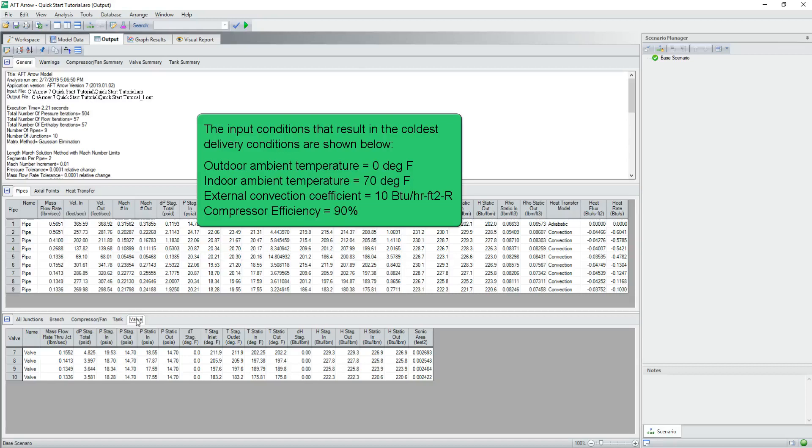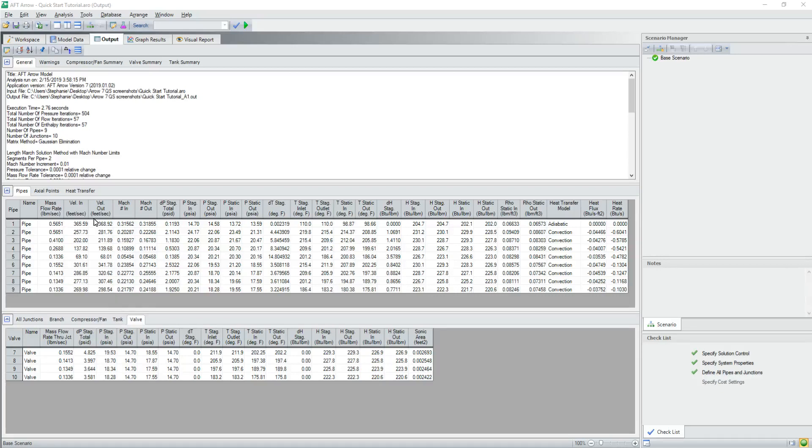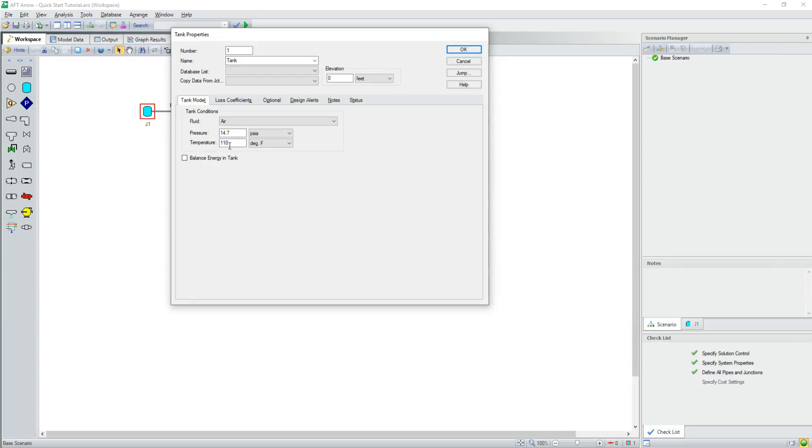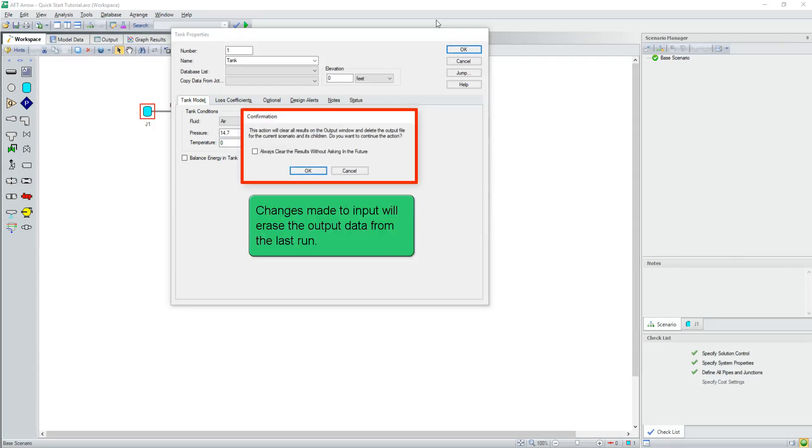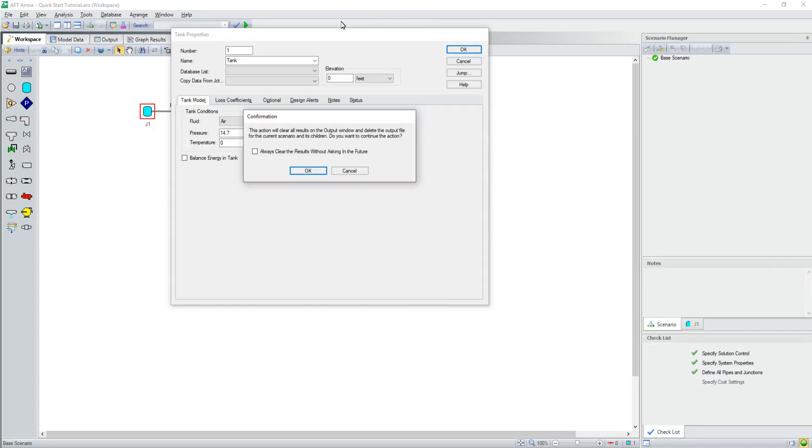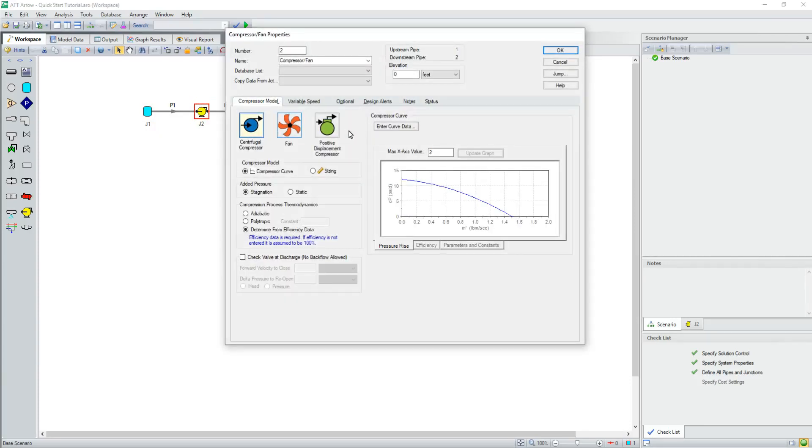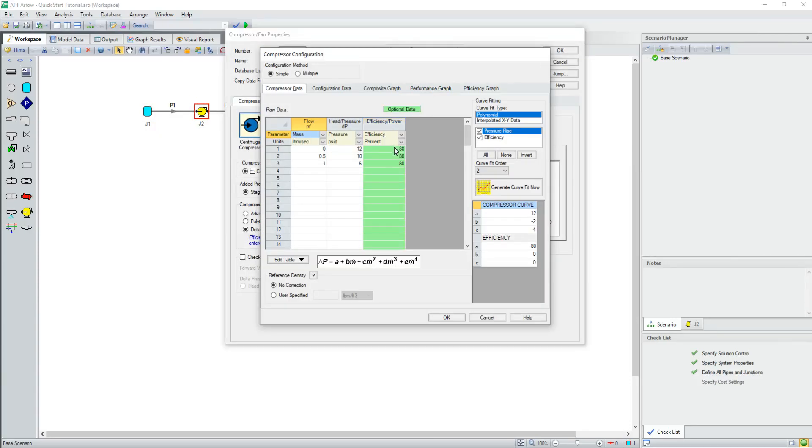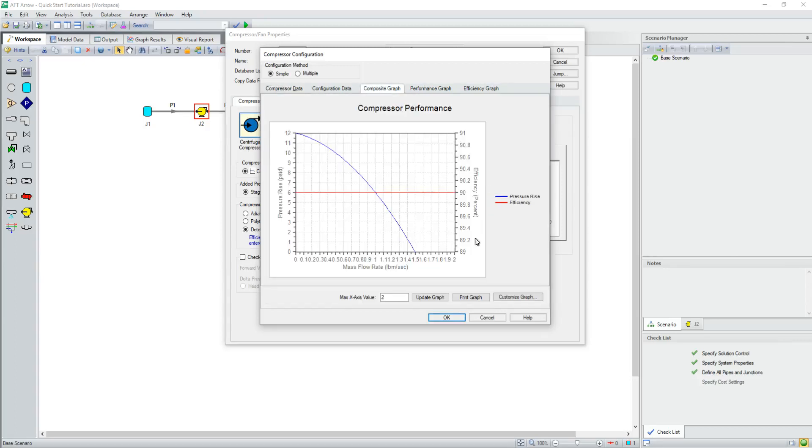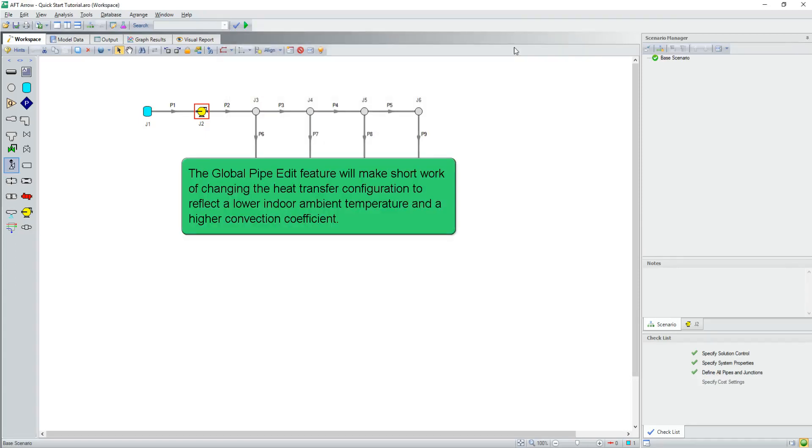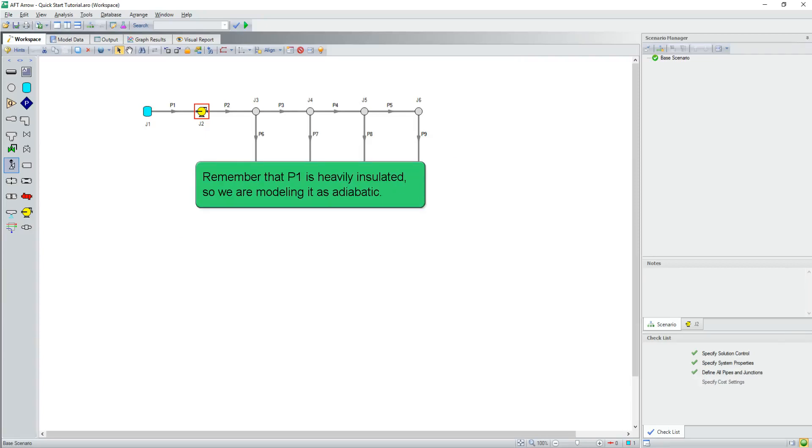The input conditions that result in the coldest delivery conditions are shown below. It's important to note that changes made to any input data will erase output data from the last run. The global pipe edit feature will make short work of changing the heat transfer configuration to reflect a lower indoor ambient temperature and a higher convection coefficient. Remember that P1 is heavily insulated, so we are modeling it as adiabatic.